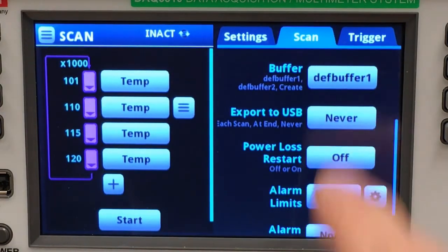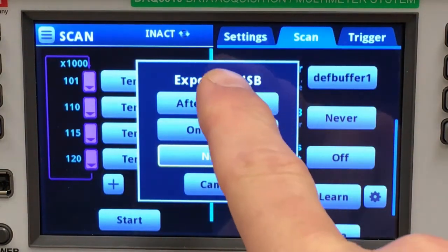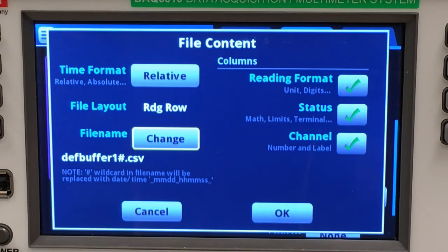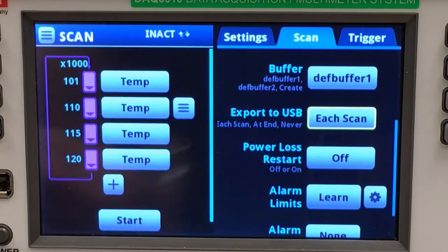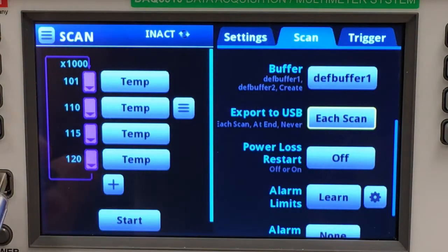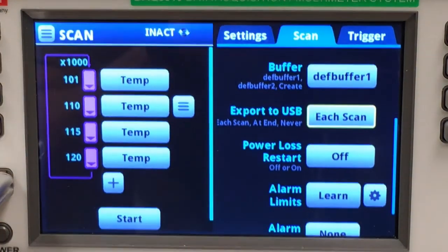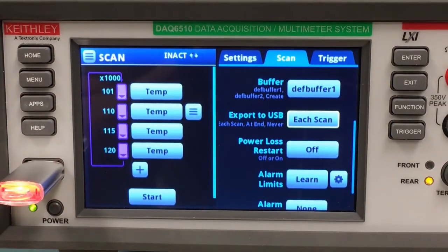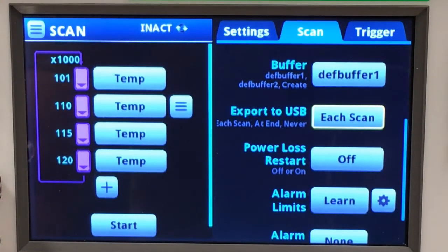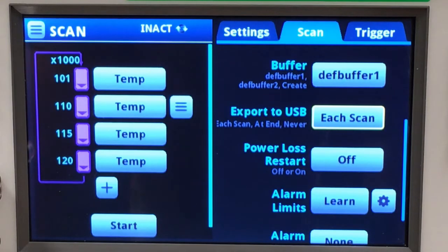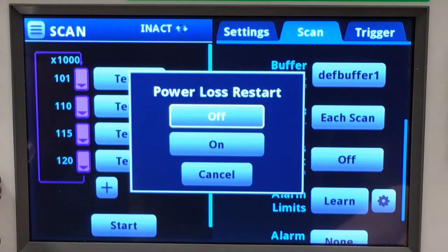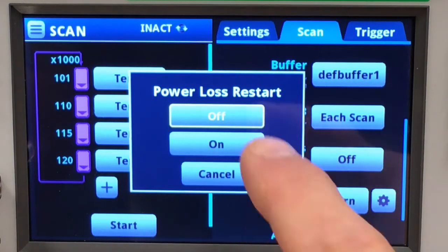During the scan, I wish to export the data after each scan to an external USB drive. I will accept all my file defaults. I'll take my USB drive and place it into the front of the DAQ 6510. And should the power go off sometime early in the scan, I want it to restart from the very beginning without my intervention, so I will turn power loss restart on.